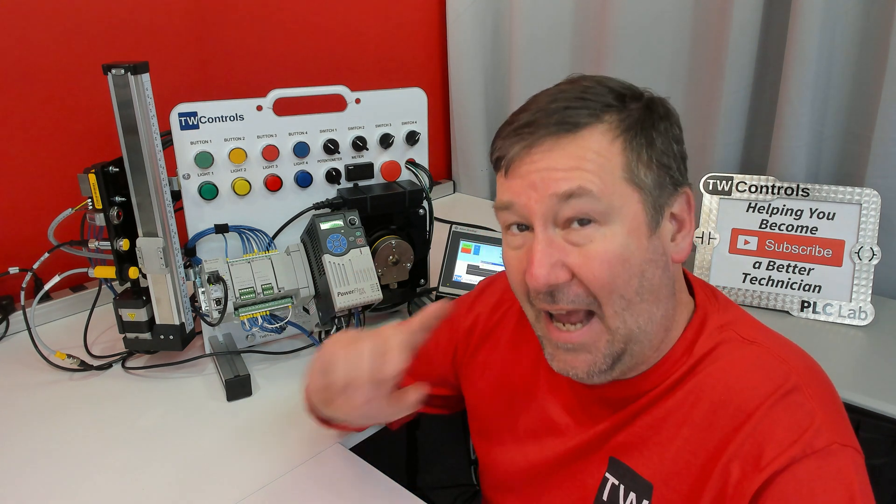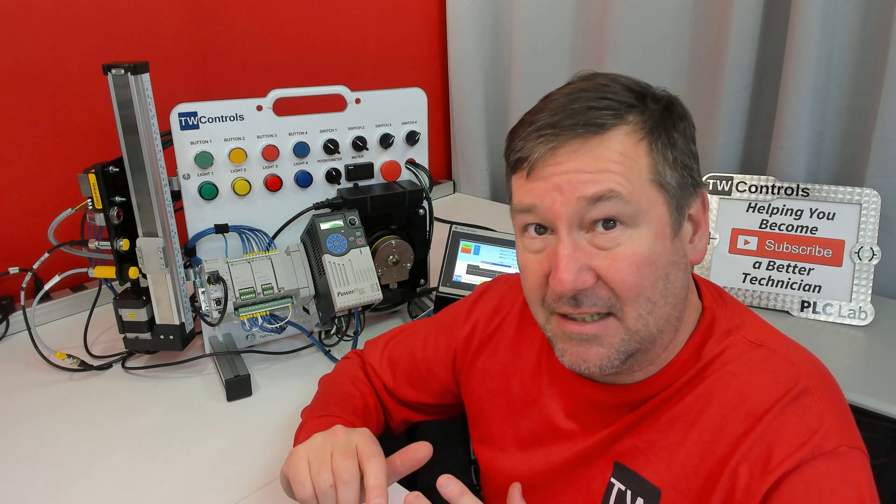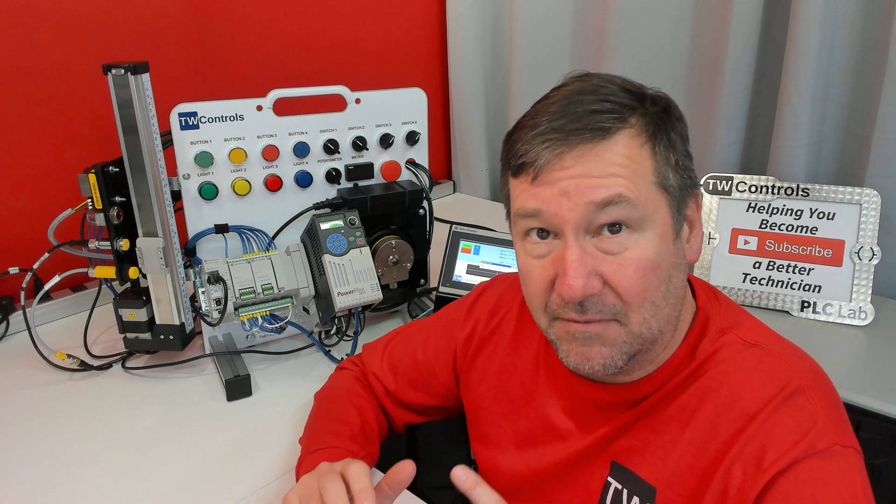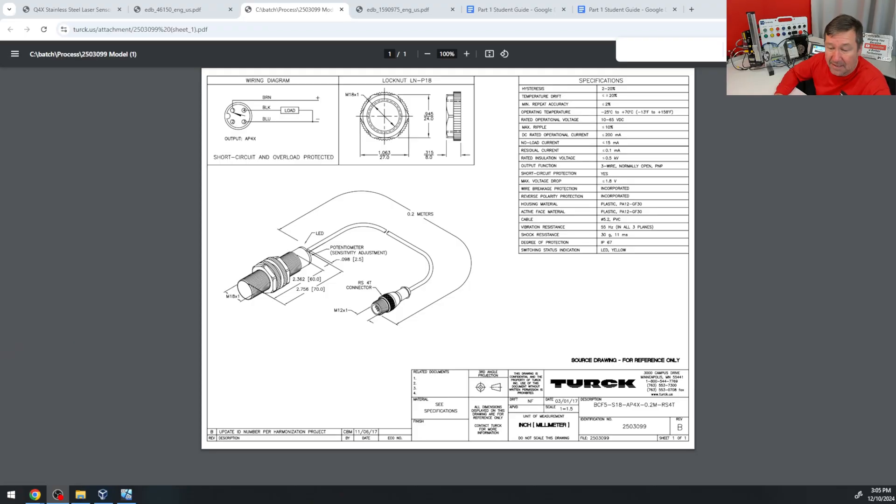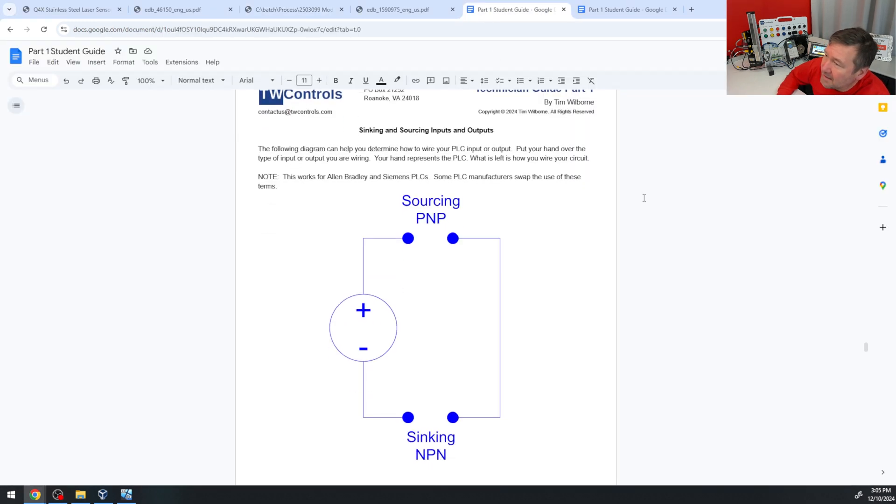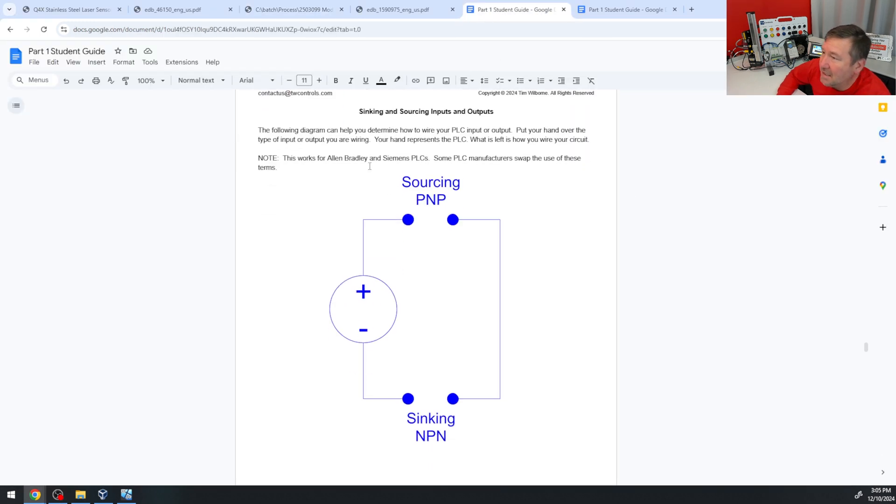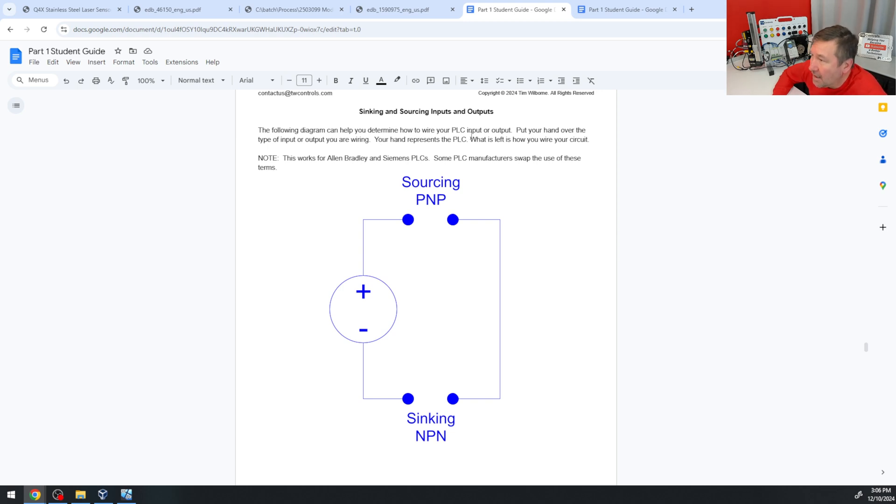And we have a video where we talk to the details of sinking versus sourcing. But in that video, which I'll put a link to the whole course series in the description where you can find it, we have this right here. And it says the following diagram can help you determine how to wire your PLC input or output. Put your hand over the type of input or output you're wiring. Your hand represents the PLC. What is left is how you wire your circuit.